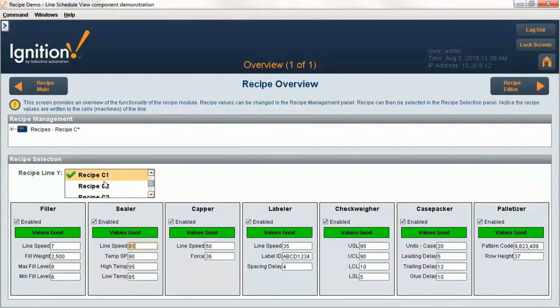Once the recipe is loaded to the PLC, we listen on those tags to see if they change. For example, on my sealer, my value is 81 right now. If I change that to 95, you'll see that a variance exists. We track that because the set point could change in a panel view or in programming software outside of Ignition, and if it differs from what we loaded down, we want to know about that and report it so we can see these variances.